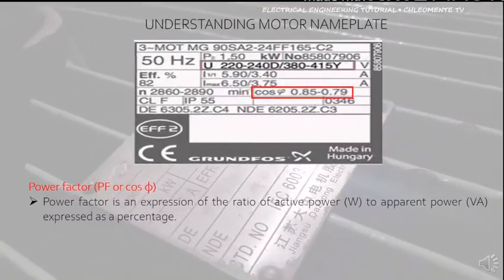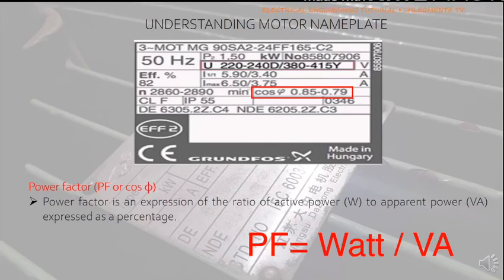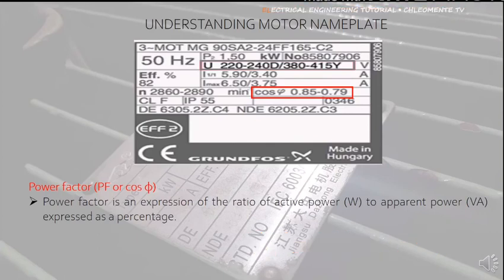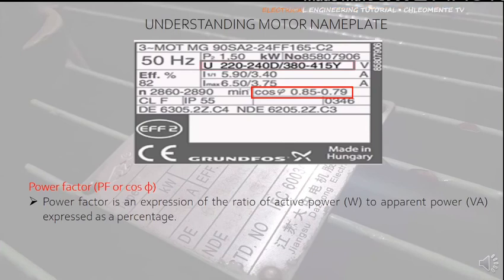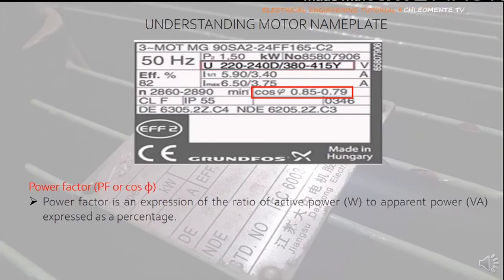Power Factor, denoted by PF or cos φ, is an expression of the ratio of active power (W) to apparent power (VA), expressed as a percentage. This data indicates the percentage of useful energy from the total energy. When the motor runs at low power factor, its efficiency is affected, meaning there are more losses. The power factor of a motor is lower when it is operating underloaded — it reduces when the motor is below 75% of its rated load. It is best practice to keep the motor running at a power factor of 85%.